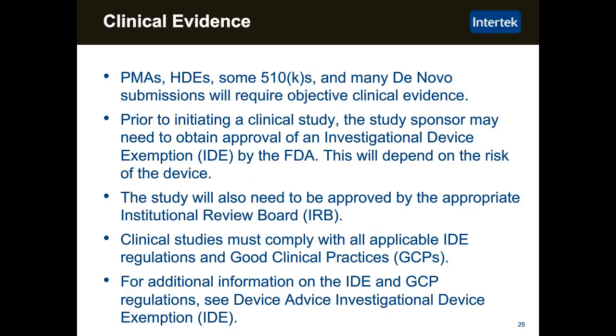Clinical evidence is another area where PMAs, HDEs, some 510Ks, and many de novo submissions are going to require objective clinical evidence. Now, prior to initiating a clinical study, the study sponsor may need to obtain approval of an investigational device exemption by the FDA, and this is going to depend on the risk of the device. So what needs to happen is you and an institutional review board need to make a decision on whether a device is a significant risk device or a non-significant risk device. And there is guidance from the FDA on this. And in the event that the institutional review board may not agree with your assessment on the risk of the device, you can approach the FDA and they will give you a decision on whether or not they think it is a significant risk device.